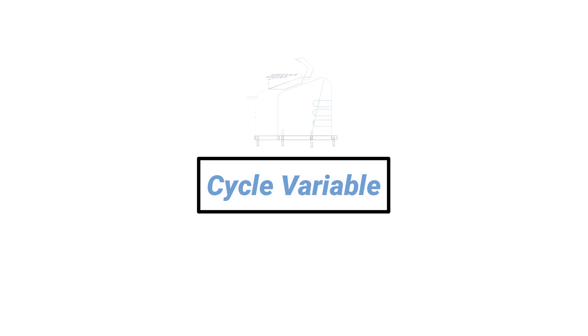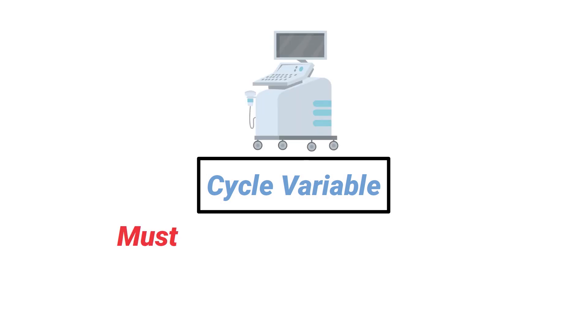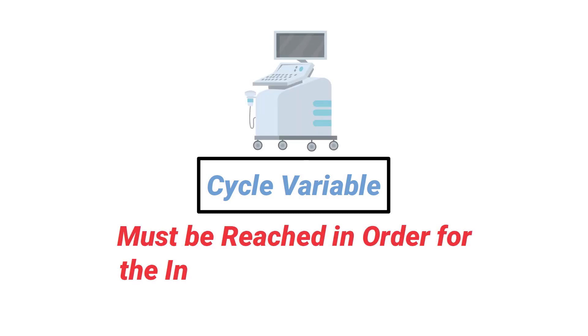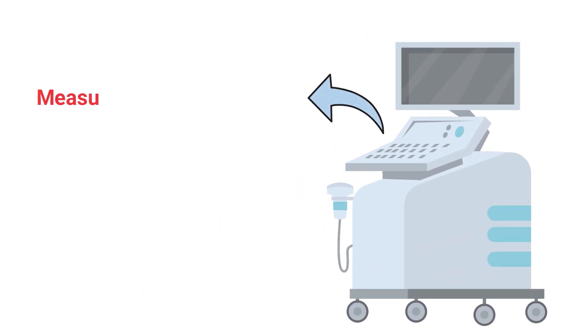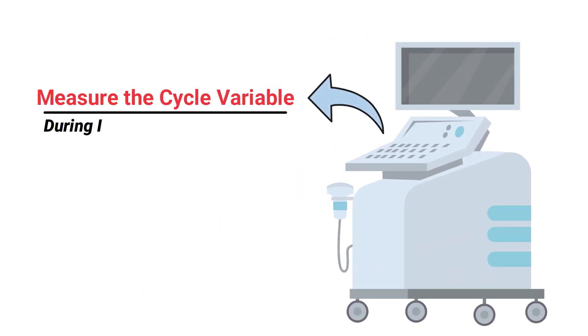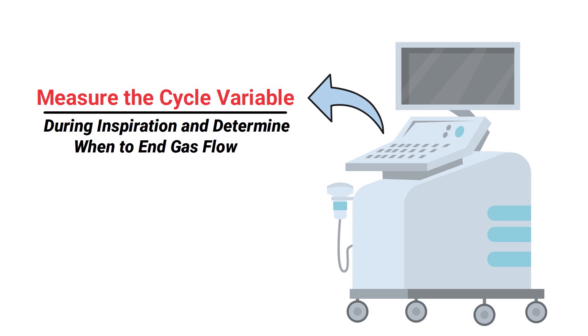A cycle variable on the mechanical ventilator must be reached in order for the inspiratory phase to end. The machine is able to measure the cycle variable during inspiration and determine when to end gas flow to transition to the expiratory phase.